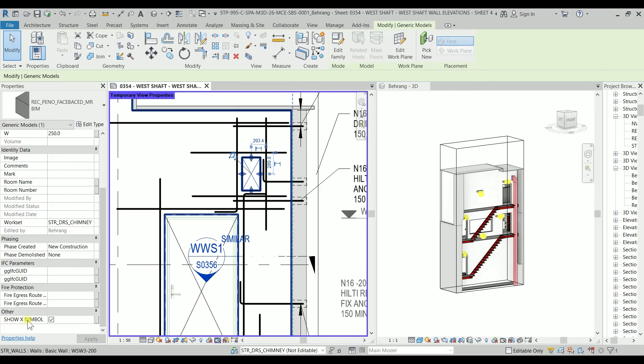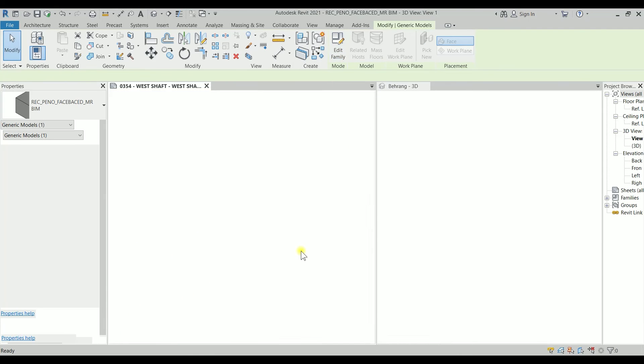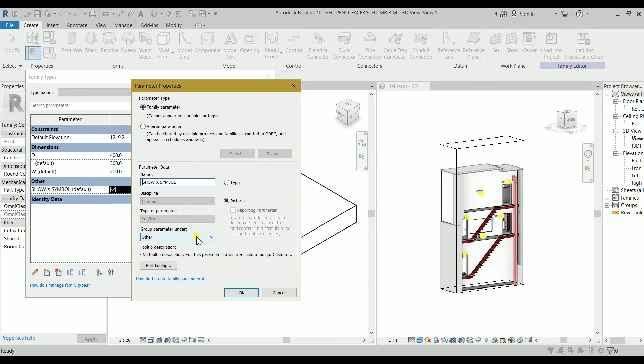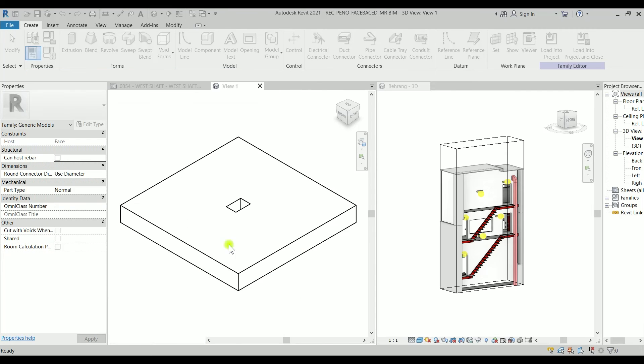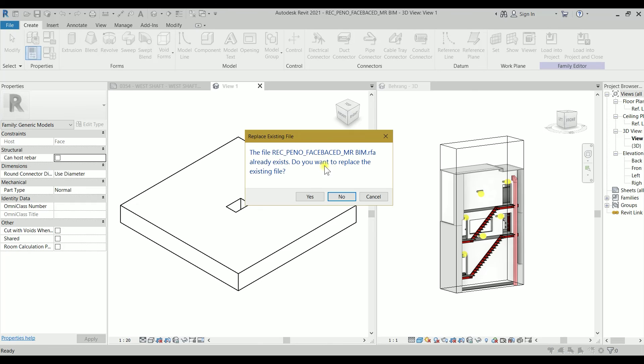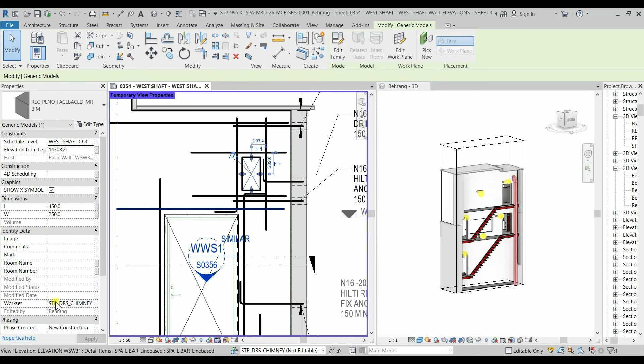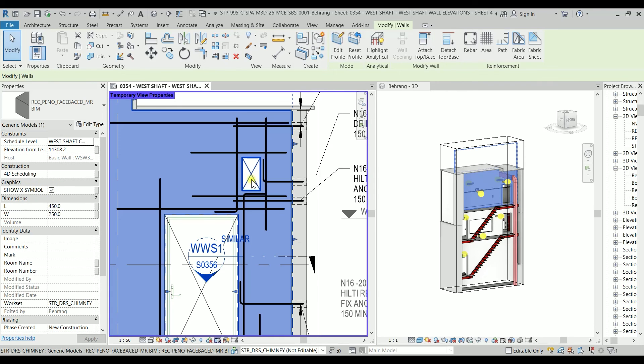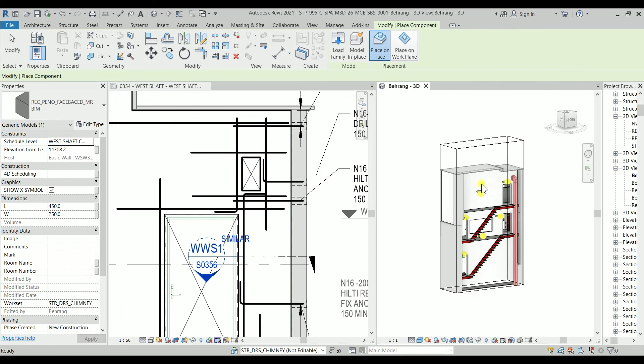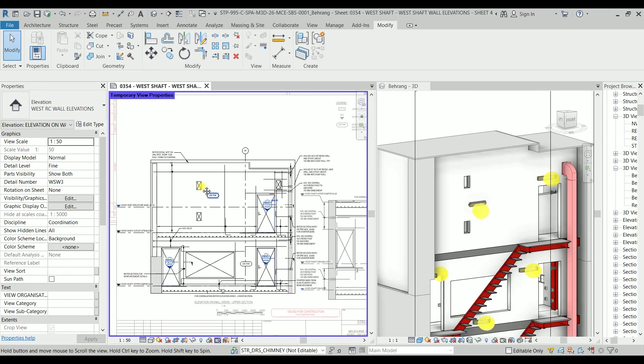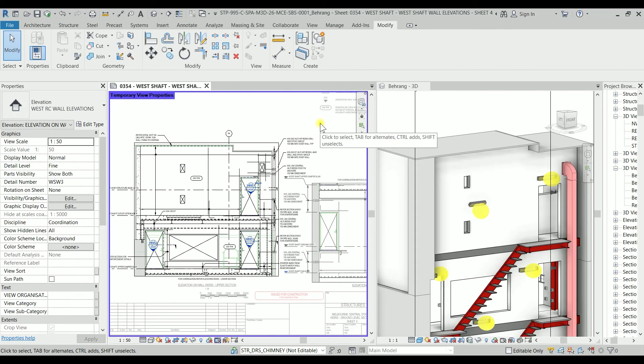Turning off the mechanical model, it looks nice and clean — we have a penetration there, and we have the option to turn the X symbol on or off. I'll edit the family, go to Family Types, edit the Show X Symbol parameter and move it to the Graphics group, then load it back to the project — saving and overriding the existing version. Now the Show X Symbol is under Graphics. I can create similar penetrations and place them wherever I want on walls. Amazing — this is the end of the video, thank you so much for watching.